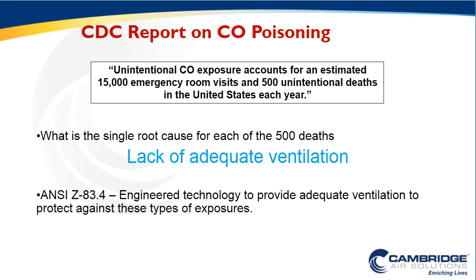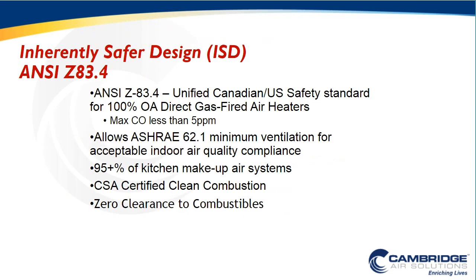And these products are certified to a very stringent safety standard, ANSI Z83.4, to ensure that we have adequate ventilation and low product combustion to be able to keep those systems safe. Really, I like to use a term that is utilized in other parts of the world when we talk about engineering safety systems, which is inherently safer design. And that's at the core concept of the safety standard of the ANSI Z83.4: to make sure that we do not require engineering controls to make it safe, but actually the ventilation component of these devices makes it inherently safe, such that we will always be ventilating and we can never create an indoor concentration above the discharge concentration of CO.